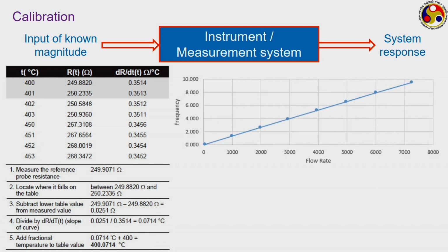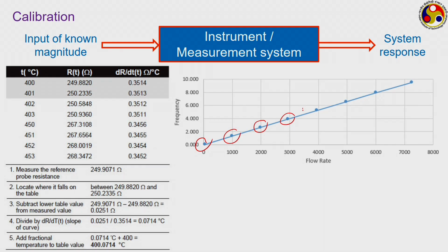Even more popular approach is to get a calibration curve like this, where your input, like here the input in this example is flow rate, but output is coming in terms of frequency of some instrument. So, these are the points where we have taken the reading, some known flow rate, corresponding frequency we have measured, and we have tried to represent them with a straight line or some other suitable curve. Then when we measure some unknown quantity, unknown flow rate, say the corresponding frequency is falling here, then easily from the curve we can identify the flow rate. So, this calibration curve generation is a must for any instrument to start with.